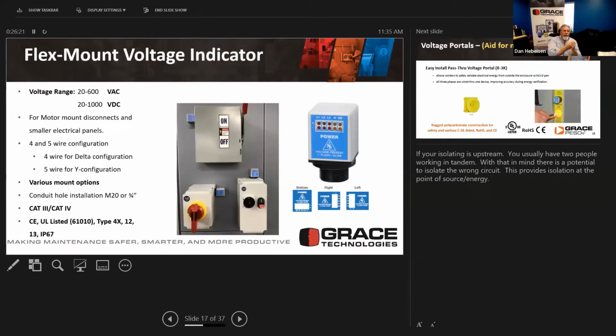We realize that not all the equipment gets mounted onto an MCC or an industrial control cabinet. There are a lot of individual panels on various production environments and on the shop floor. And we've got a couple of different opportunities there to put these at smaller disconnects, just a simple power yes, power no, to give you the visual indication at those small disconnects. So whether it be a small rotary type or the lever type, could be on lighting panels, all sorts of different things. These are also available in a 4-wire or a 5-wire. And again, the Cat 3 and Cat 4 and UL listed to 61010, type 4, 4X, 12, 13, all the way up to an IP67 rating.